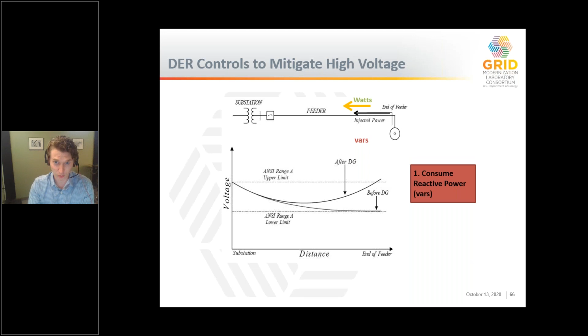The second way is less preferable, and that's to reduce the active power, or watts, the part of power that a customer or DER owner is compensated for. This is generally reserved as a backup option. We'll talk later about how these reactive and active power functions can be stacked, so there's a primary response related to reactive power, which doesn't affect the output of the device if it's designed properly, and then as a backup, curtailing the power in real time.